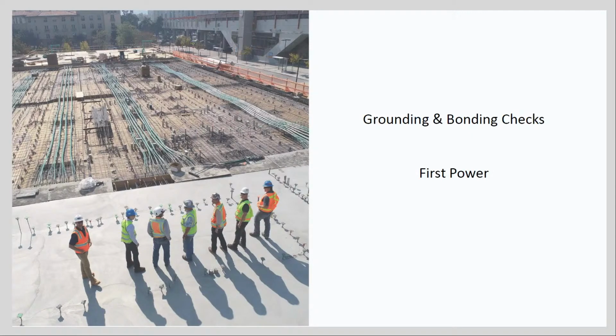Once the cubicles are energized for the first time, then some of the initial pre-commissioning checks can take place, and this would include communication checks to other cubicles. So if there's a suite of, say, a dozen cubicles, they're all going to be communicating amongst each other, and you want to have some of the basic checks to just make sure that the cubicles are responding to the communications network. Remote I/O checks to distributed devices within the plant, as well as communication with each of the cubicles back to the central control room.